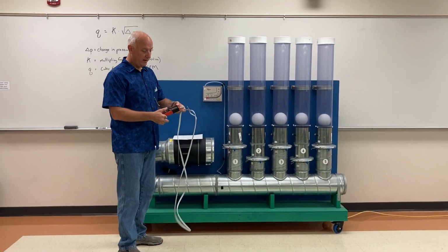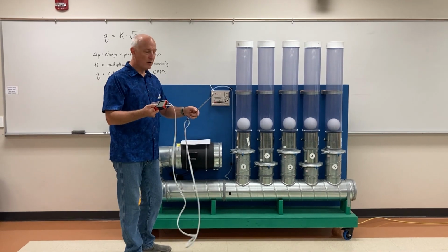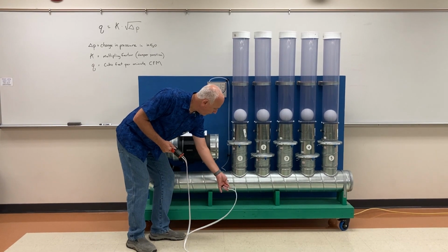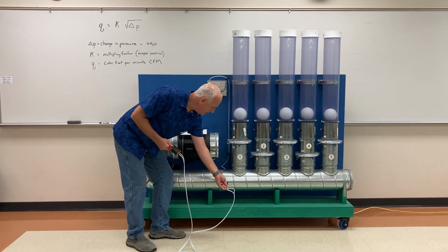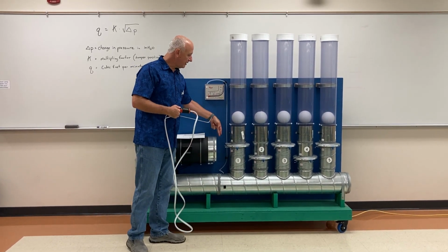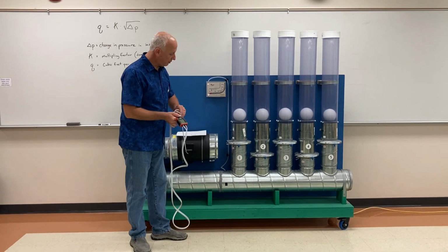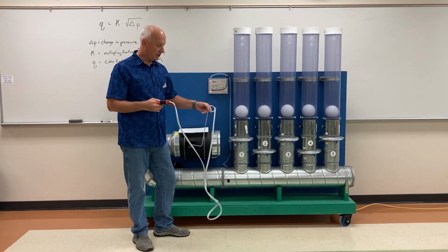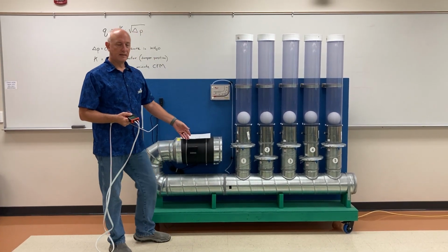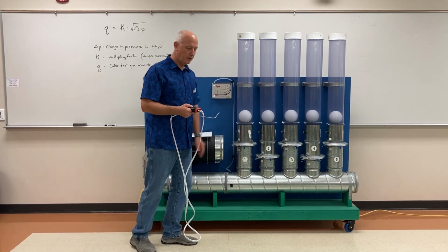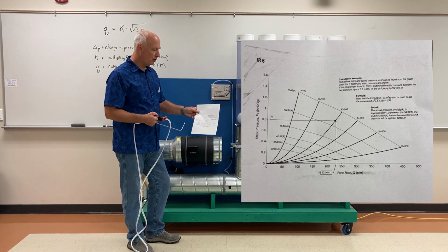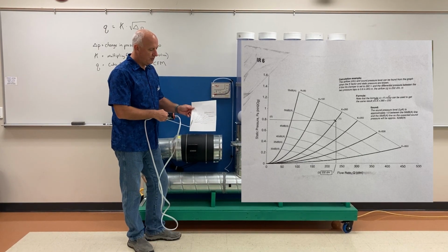So I have the meter back. I have it set on inches of water again, and I've hooked the pitot tube up to it, and you would stick it in there and point it toward the fan, and you would take multiple readings. You have to calculate where precisely the readings are across and where the readings would be in a vertical position. And then you take those measurements and run them through another formula to calculate the quantity or the CFM going through the ductwork.